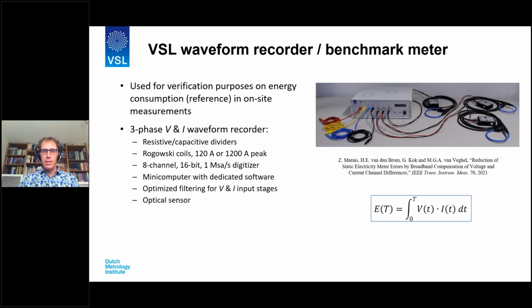It is a three-phase waveform recorder with broadband components and special matched input filters between voltage and current signals, such that they are properly multiplied in the integral equation. It also measures energy continuously, but can be used to record voltage and current waveforms at specific time intervals, or when triggered by specific threshold values of the THD, the crest factor, or other parameters.